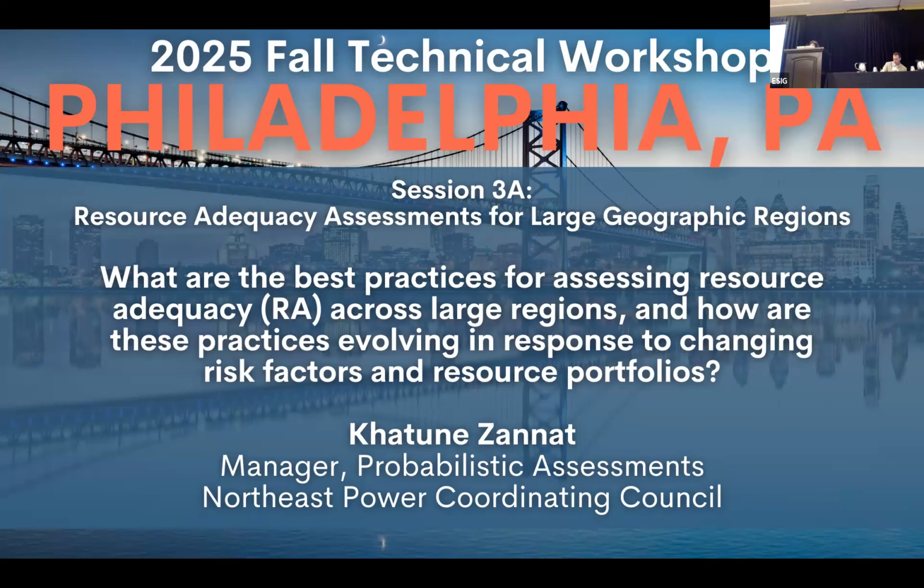Similar to NERC, evaluating resource adequacy as well as emerging risks for all of North America, each year NPCC produces and publishes about 4 reports covering the NPCC region. These reports are the pre-seasonal reliability assessments covering summer and winter. We use a probabilistic method to complement our deterministic assessment of the summer and winter. That's our seasonal assessment.